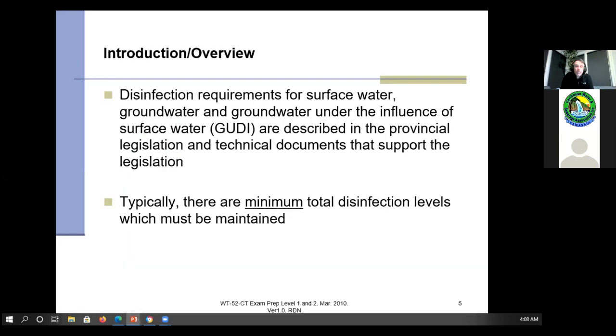Disinfection is required for surface water and some groundwater. In the past, groundwater didn't always have to be disinfected because it had very limited interaction with the surface. Surface water has a lot of contamination that can happen because humans are in contact with it. We also talked a little bit about groundwater that's under the influence of surface water — they call that GWUDI. That shows up on the test sometimes. GWUDI means the water is not in the ground long enough when it goes to your well; it might be fed from a nearby stream or river and goes too quickly, so we have to treat it like surface water.